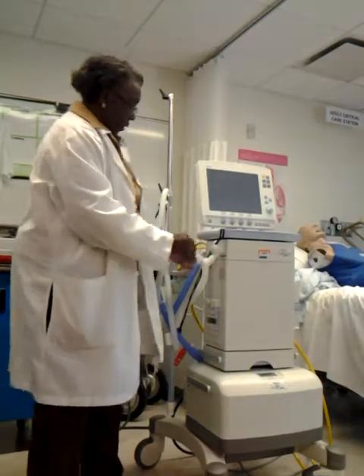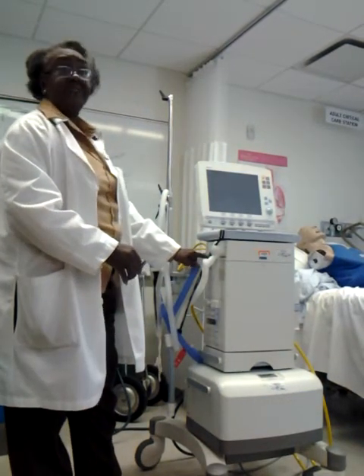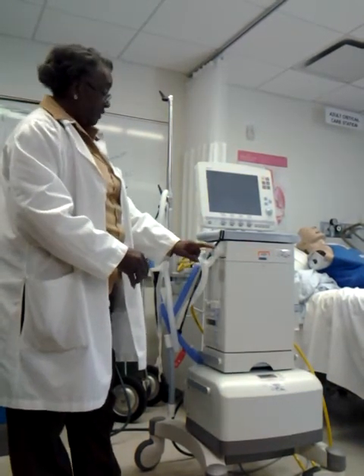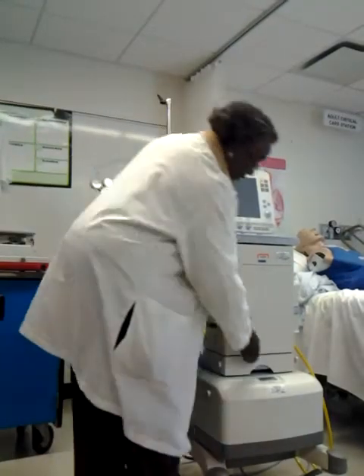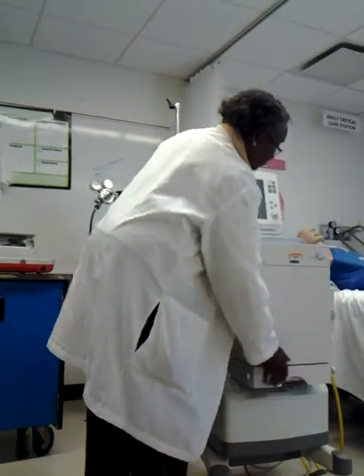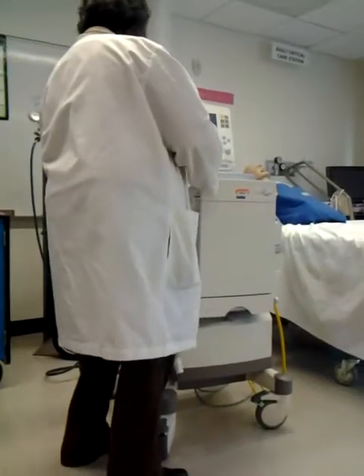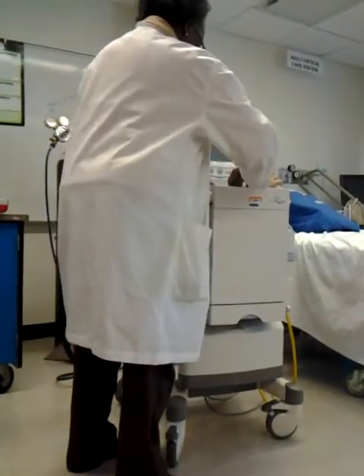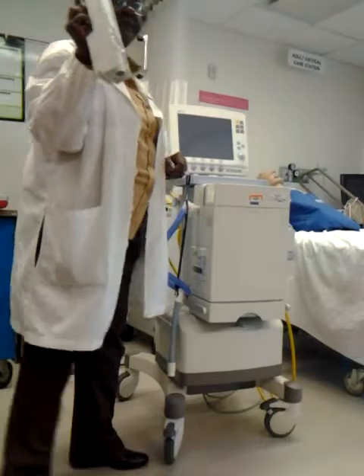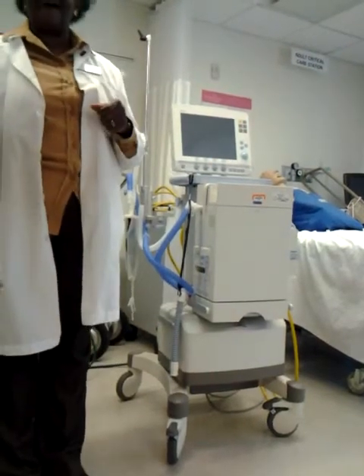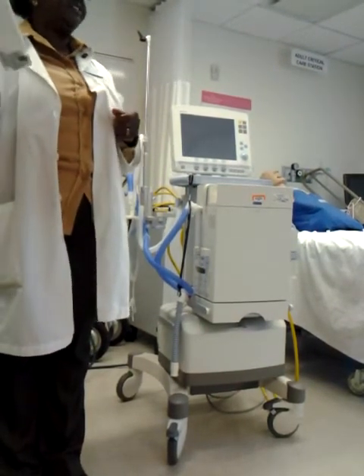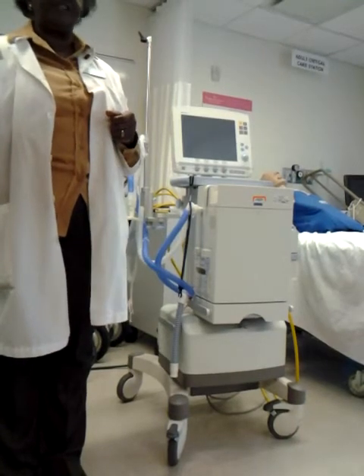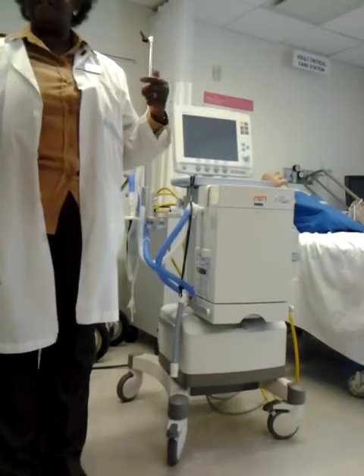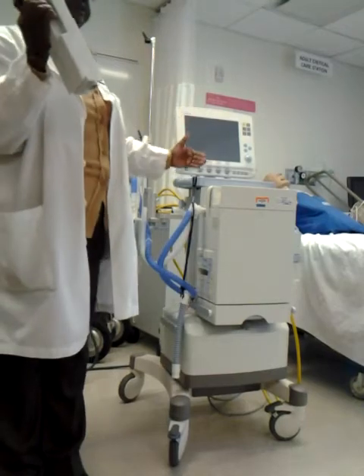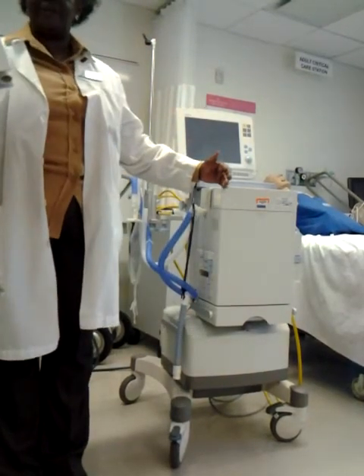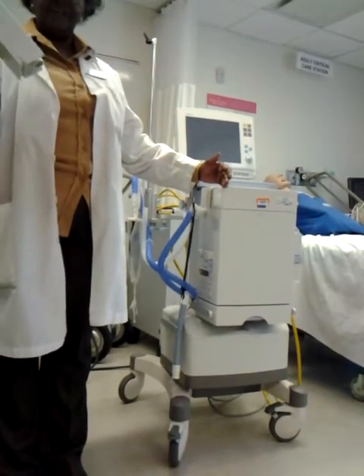Your inspiratory limb, and there's a little man here with an arrow that shows you inspiration. This is your expiratory limb. One of the most important components of your Servo is your expiratory valve. The expiratory valve comes out and it can be cleaned. And inside this you have a flow and pressure transducer. Remember we said with all of your ventilators with the closed system, you measure flow and pressure on the inspiratory side as well as on the expiratory side. And this is your flow, and it has it all in here.